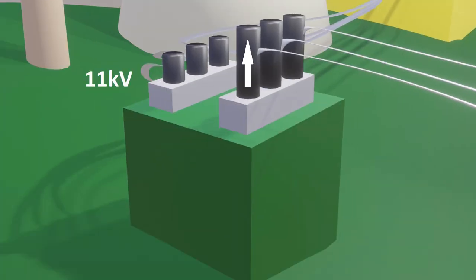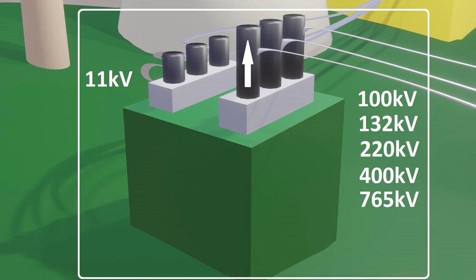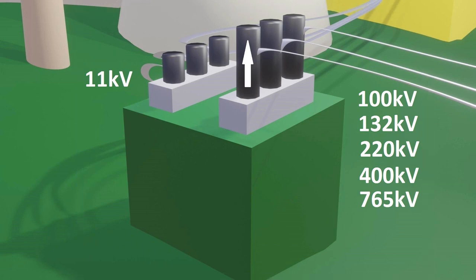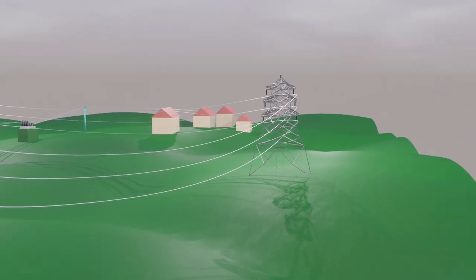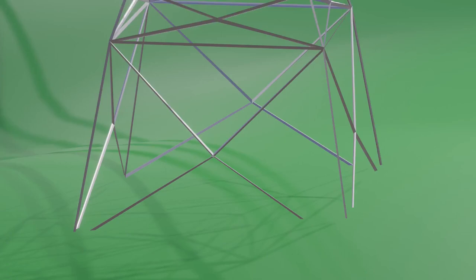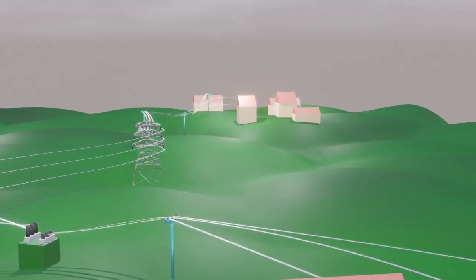This 11 kV level is stepped up to 100 kV, 132 kV, 220 kV, 400 kV, and 765 kV using power transformers installed at substations. So the 11,000 volts level is stepped up to extra high voltage levels such as 100,000 volts, 132,000 volts, 220,000 volts, 400,000 volts, and 765,000 volts. Then this extra high voltage electricity is transmitted over long distances using long conductors supported by huge towers. This system of conductors and towers is called a transmission line.